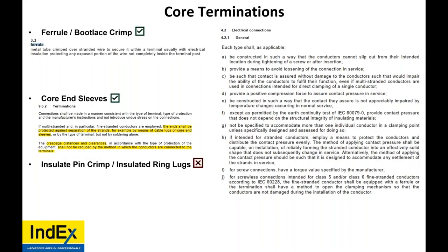Now, why do we use ferrules? Well, in the standard for -0, it says ferrule: metal tube crimped over to secure it, has insulating protection. Any exposed portion of the wire are not completely inside the terminal post. So the insulation is not being crimped on and the metal is not exposed. I think we showed pictures of insulated pin crimps with metal exposed.